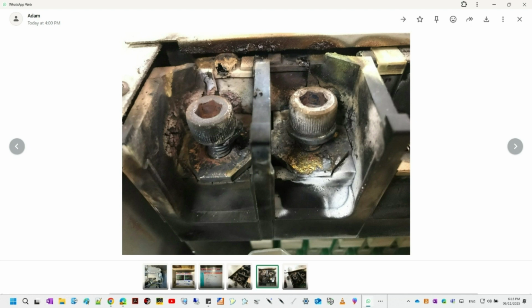Right, the I²R losses. Exactly. So even a small increase in resistance generates a disproportionate amount of heat because the current term is squared. Now, this initial heat then causes the metal terminals, the bolt, the cable lug, and the surrounding insulation to expand, maybe deform slightly, and oxidize faster. And all of that further increases the resistance at that very connection point. I see. So the heat itself makes the resistance go up, which then generates even more heat because the resistance is higher, which makes the resistance go up even more. Exactly. It's a vicious self-reinforcing cycle.